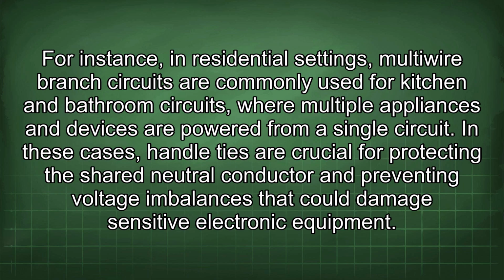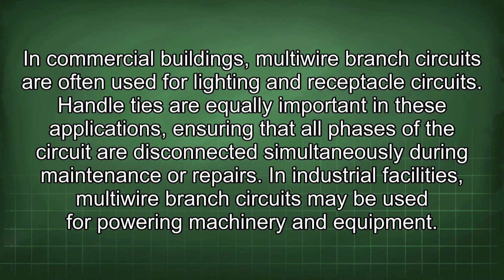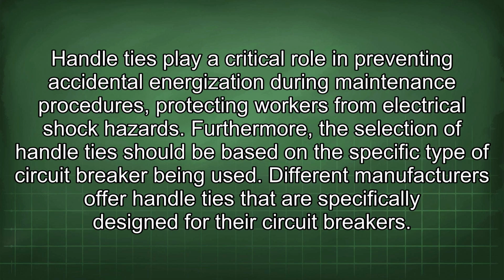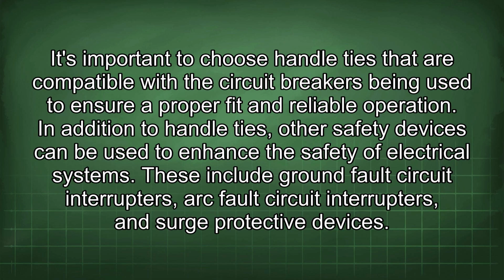In these cases, handle ties are crucial for protecting the shared neutral conductor and preventing voltage imbalances that could damage sensitive electronic equipment. In commercial buildings, multi-wire branch circuits are often used for lighting and receptacle circuits. Handle ties are equally important in these applications, ensuring that all phases of the circuit are disconnected simultaneously during maintenance or repairs. In industrial facilities, multi-wire branch circuits may be used for powering machinery and equipment. Handle ties play a critical role in preventing accidental energization during maintenance procedures, protecting workers from electrical shock hazards. Furthermore, the selection of handle ties should be based on the specific type of circuit breaker being used. Different manufacturers offer handle ties that are specifically designed for their circuit breakers. It's important to choose handle ties that are compatible with the circuit breakers being used to ensure a proper fit and reliable operation.